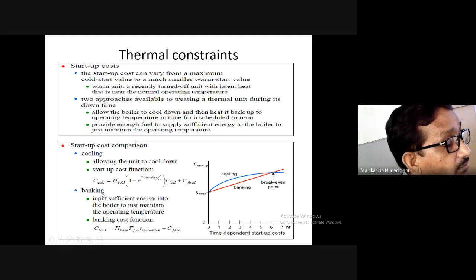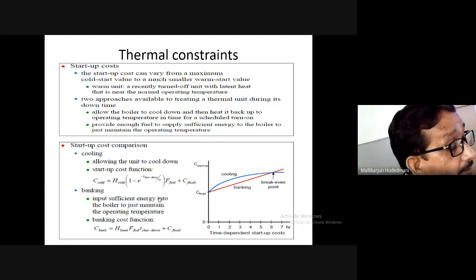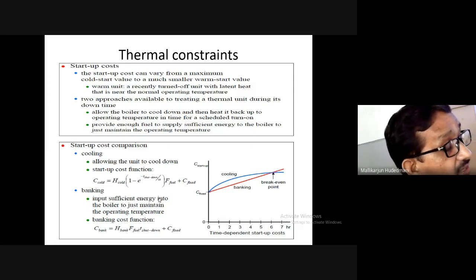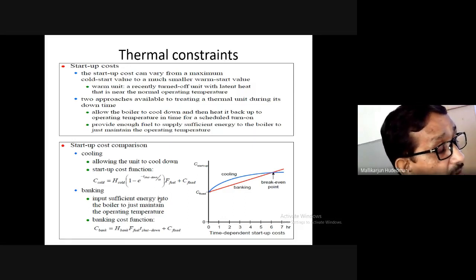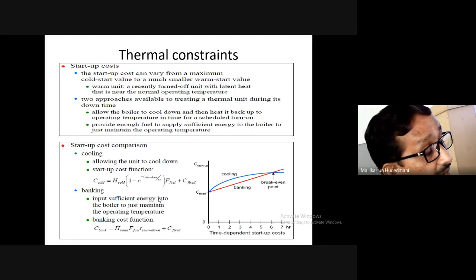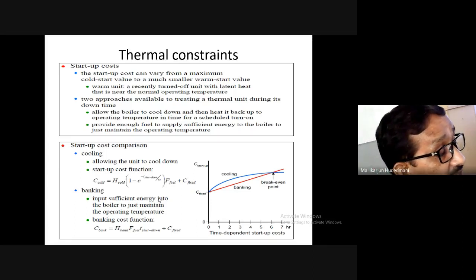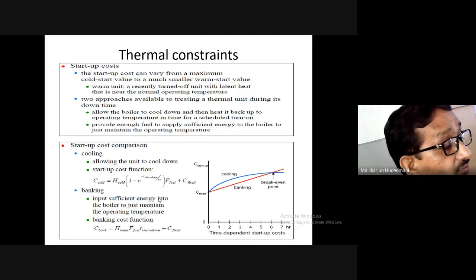Banking is nothing but a machine taken out of the schedule. Rather than cooling it down to room temperature, you maintain it at a reduced temperature, keep it running continuously with minimum input fuel, so that after a certain number of hours it can again be pulled into service. That is called banking.